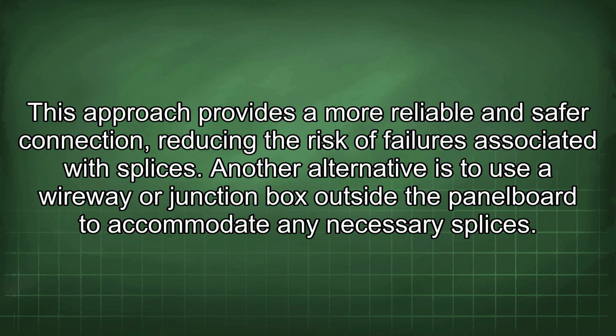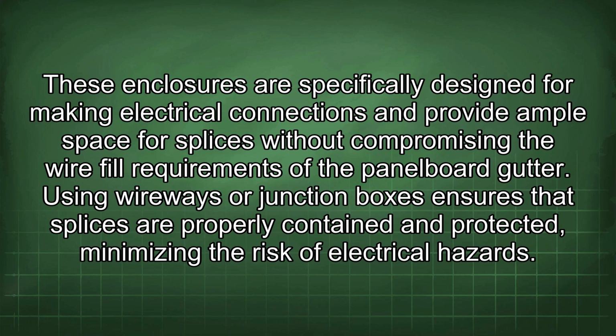Another alternative is to use a wireway or junction box outside the panelboard to accommodate any necessary splices. These enclosures are specifically designed for making electrical connections and provide ample space for splices without compromising the wire fill requirements of the panelboard gutter. Using wireways or junction boxes ensures that splices are properly contained and protected, minimizing the risk of electrical hazards.